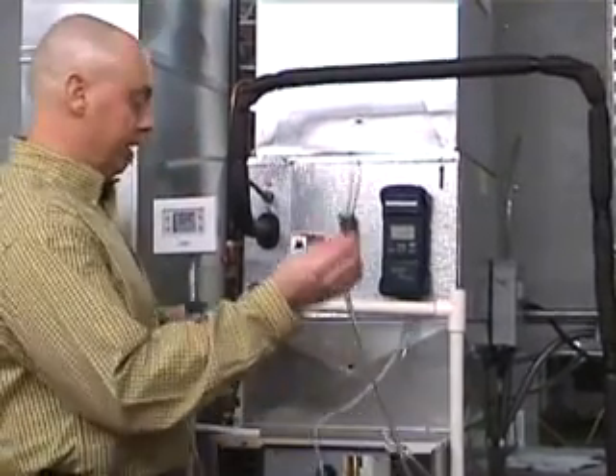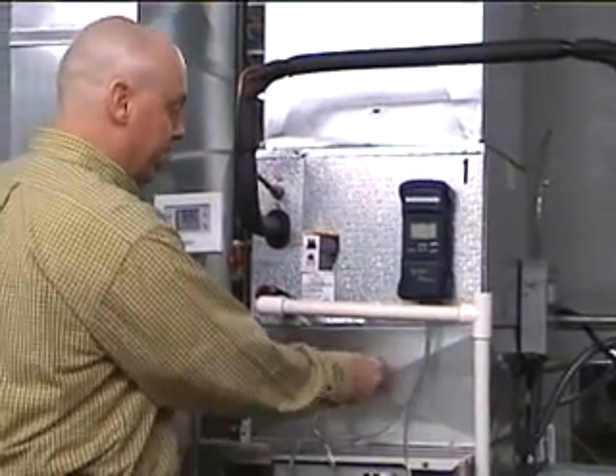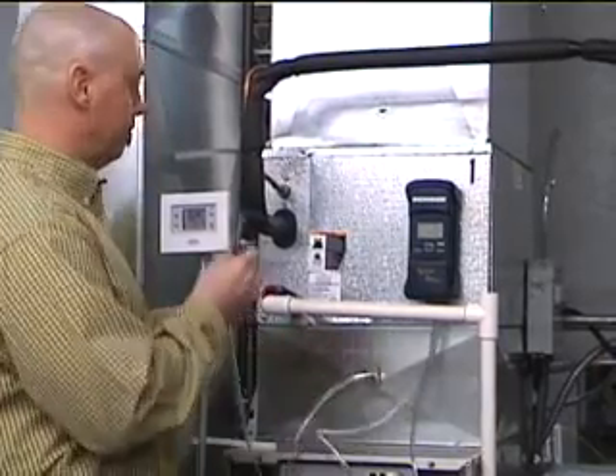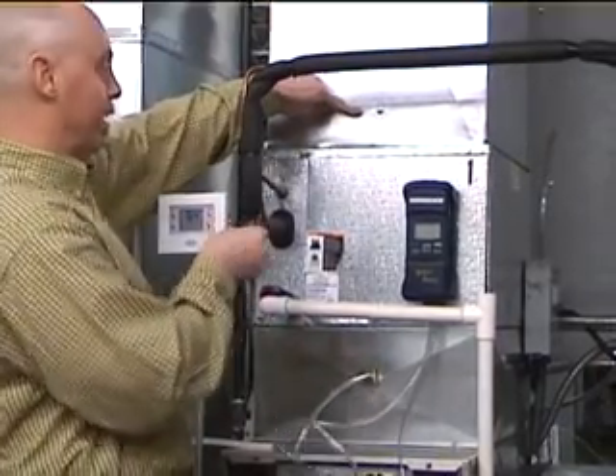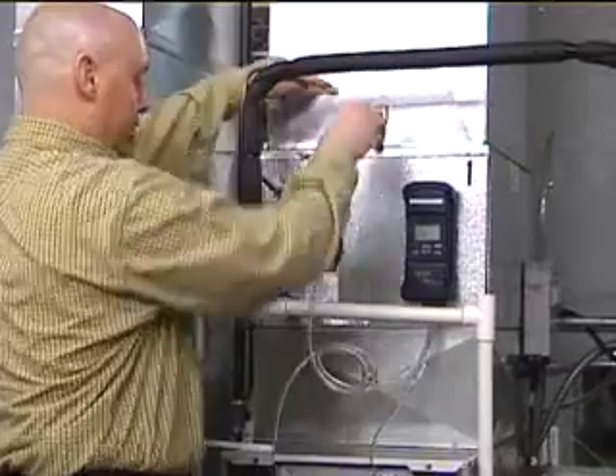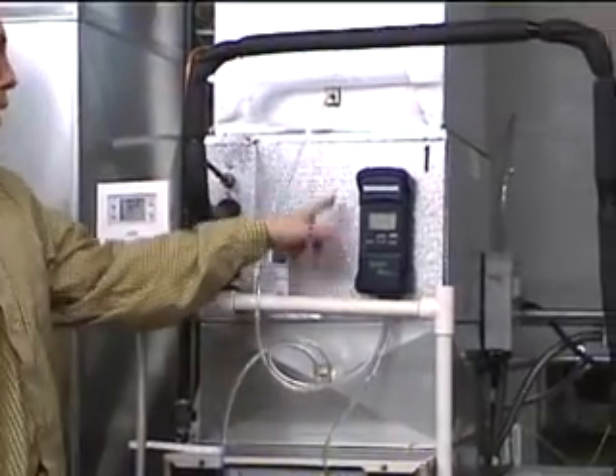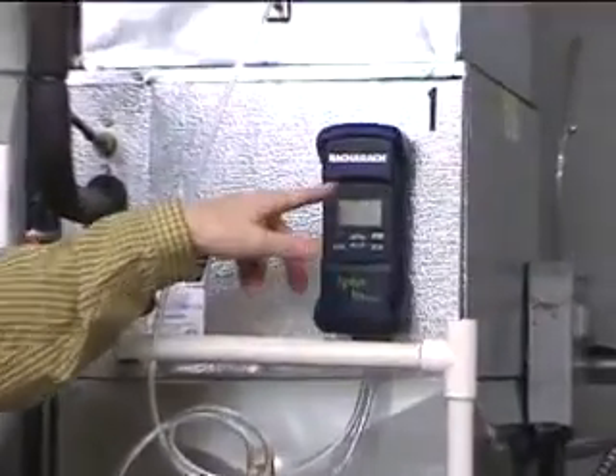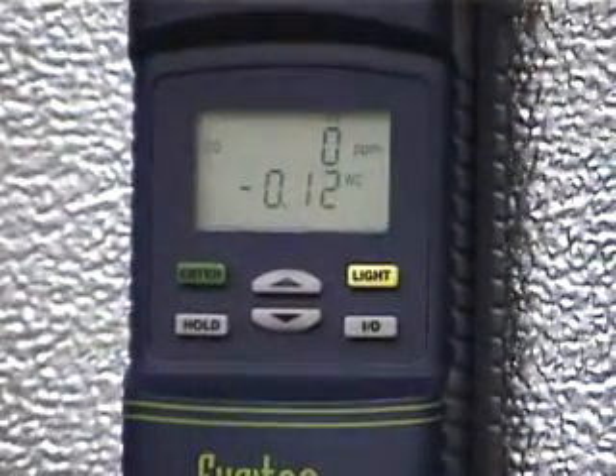Okay. So I take one of the probes, I stick it in between the furnace and the coil, and then the other probe is on the outlet of the coil. And I am reading a pressure drop across this coil of 0.12, 0.13 inches of water column. And then you can compare that to a lot of product data.